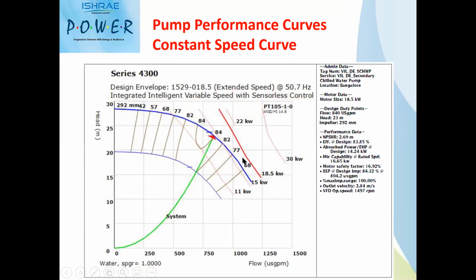So typical power curves are shown either in this way, or as my previous slide showed, there will be a separate power curve as well as an NPSH curve. So this is the best efficiency point. For this duty parameter, maybe a 6-inch pump with around 292. In this case, it is a 292 mm impeller diameter selected based on the required flow and head.